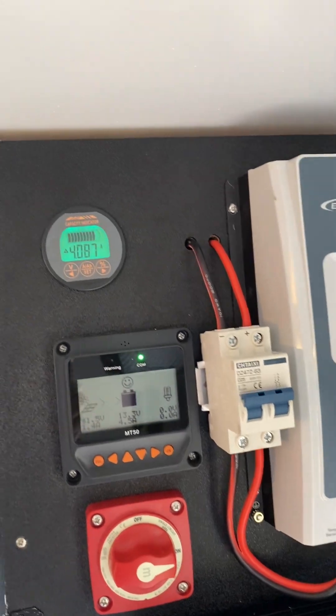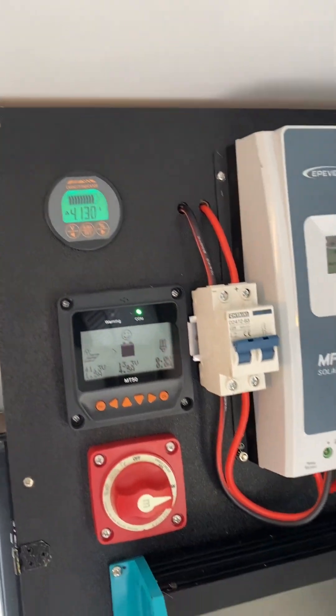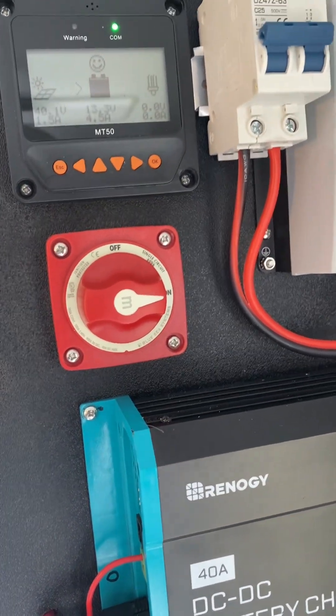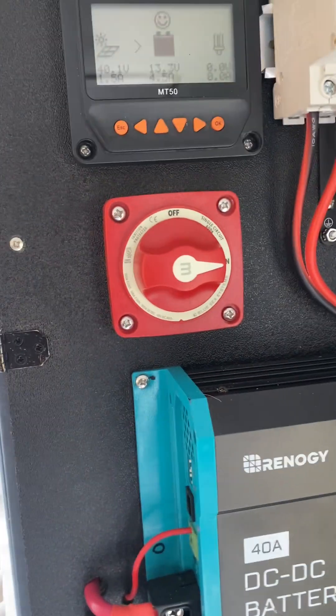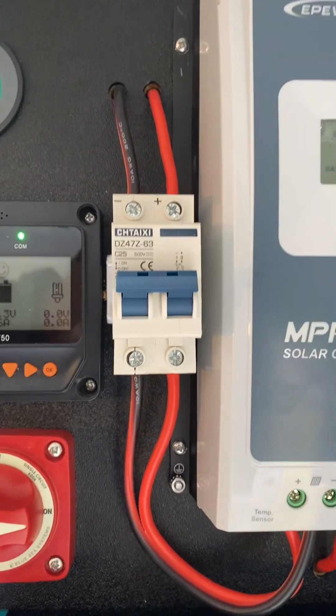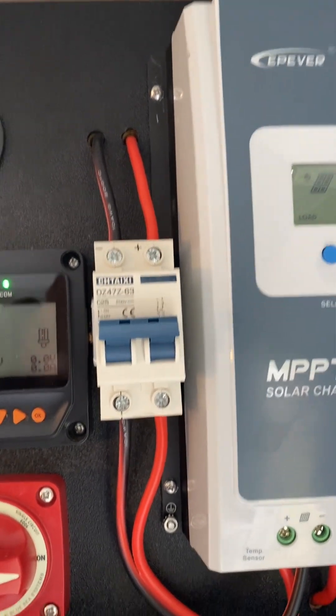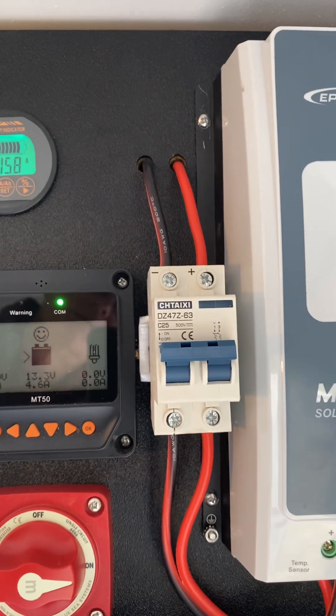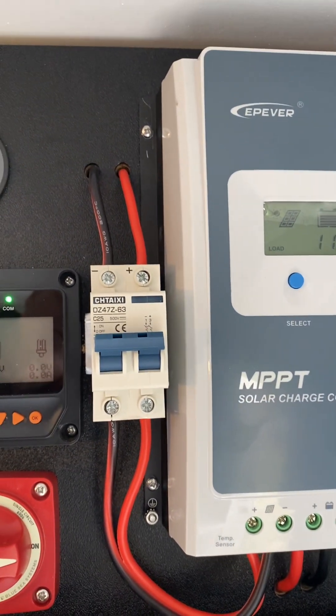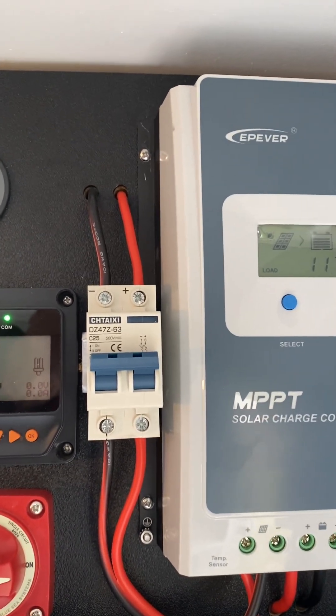It's interesting — I've got three meters here and they're all off by a couple of tenths. This is a dead man switch that shuts absolutely everything off should the end of the world come. This dual circuit breaker is a special DC circuit breaker, not AC. DC from solar panels will arc. If you have a regular circuit breaker, it'll actually weld the contacts together if it shorts out. So you need an arc-extinguishing circuit breaker, and that's what that is.